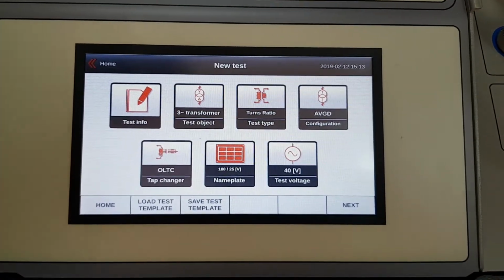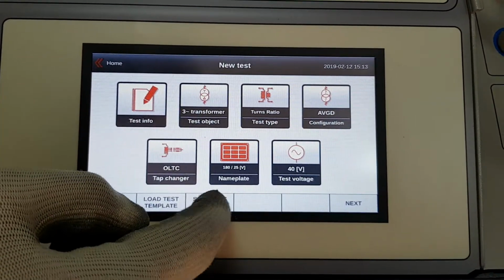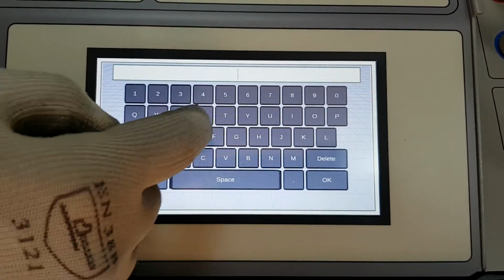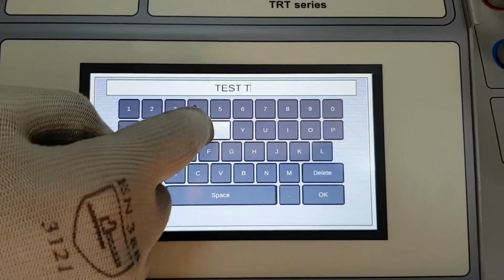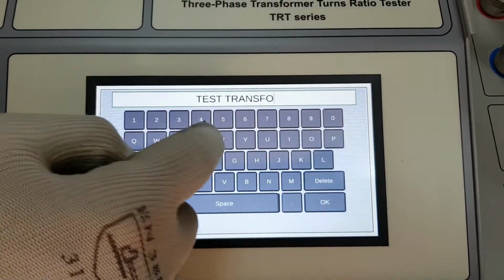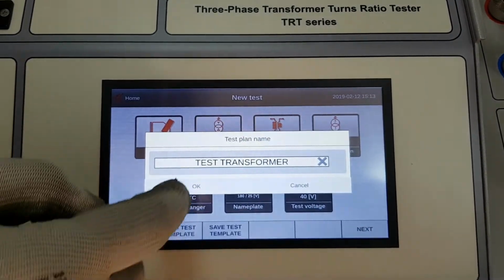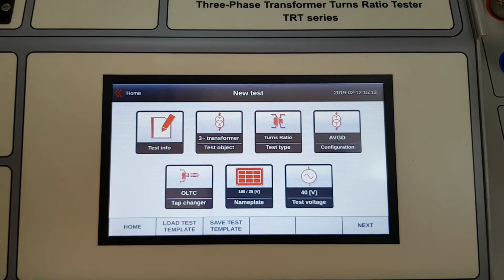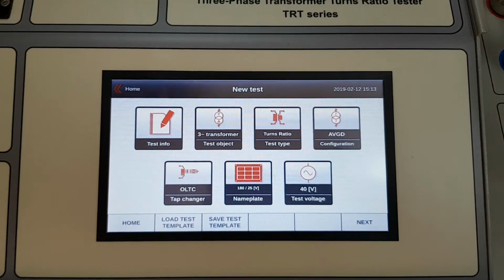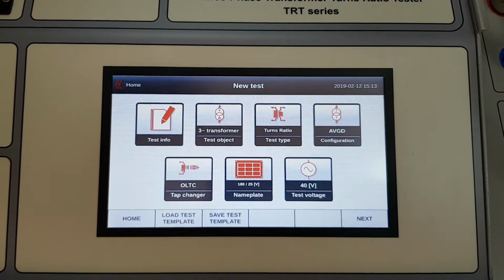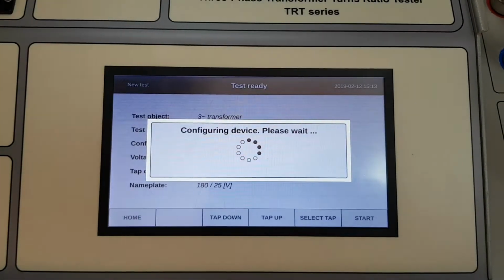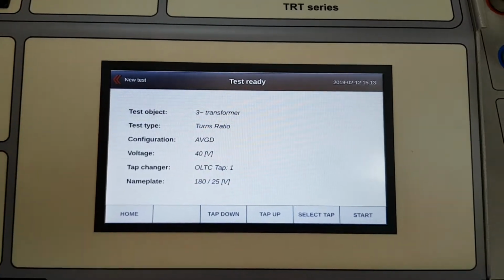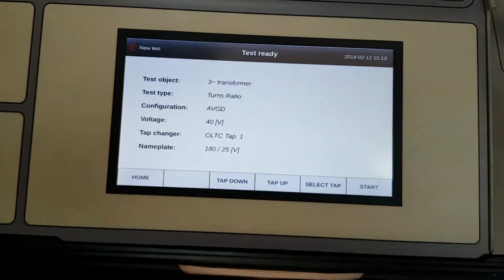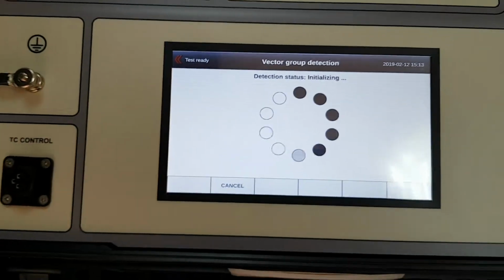And to proceed to the test, I can click next, but before I click next, I can save this configuration as a template. So if I click the save test template, and I'm going to, let's say, call it test transformer. Click OK. So now this configuration is saved as a test template, and we can recall it later on every time we want to test this transformer. So I'm going to click the next to proceed to the test, and we are ready to start the test in the first tap position.